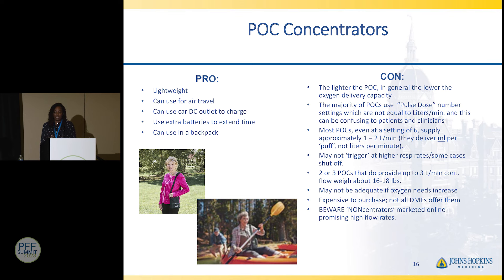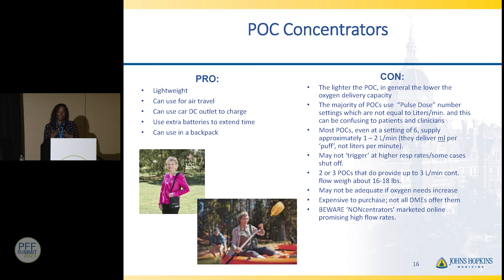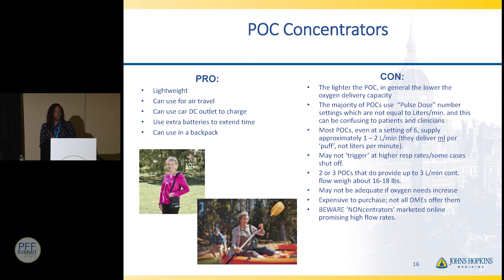Most POCs at a setting of six only deliver about 1 to 1.75 liters per minute. At higher respiratory rates, the device may trigger a shutoff, indicating the need to transition to a continuous device. This can be alarming when away from your home unit. We try to be transparent — if you're considering a POC, get tested on one prior to purchasing.